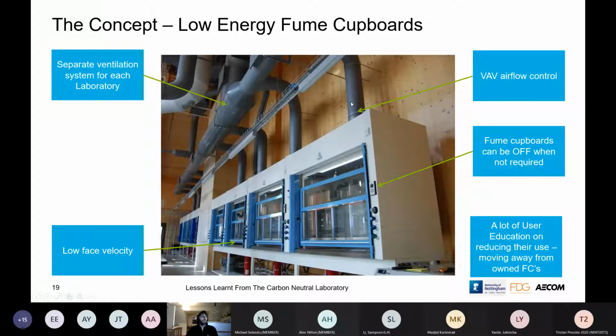They're all variable air volume, so the airflow through them varies depending on how high the sash is on the unit. Importantly, the units can be turned off. Quite often fume cupboards are designed to be kept on 24/7, which keeps using energy, but ours are designed so that when they're not used, the user can turn them off.